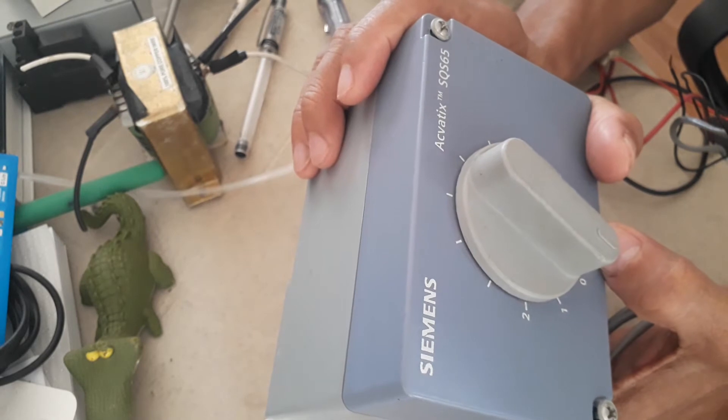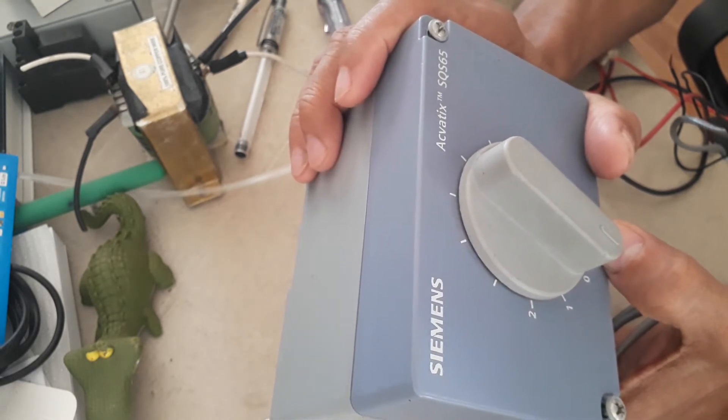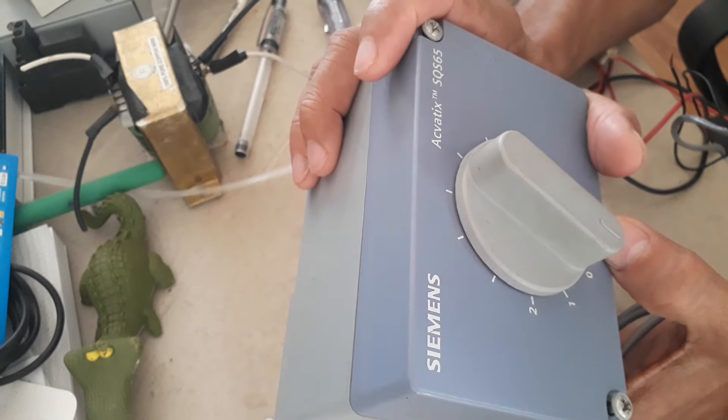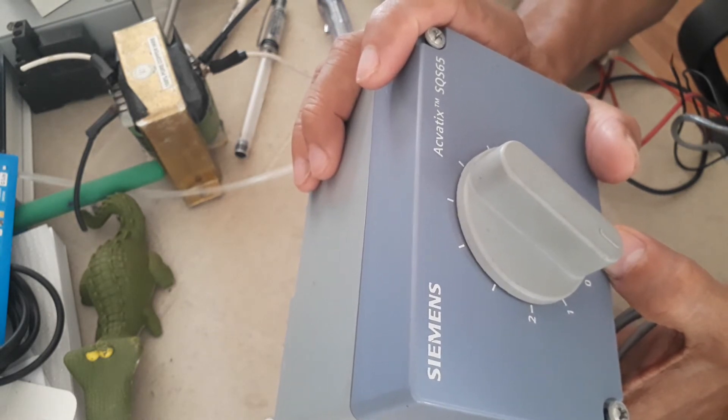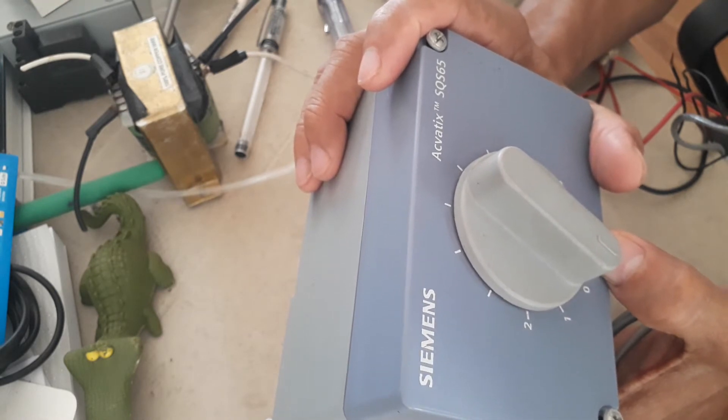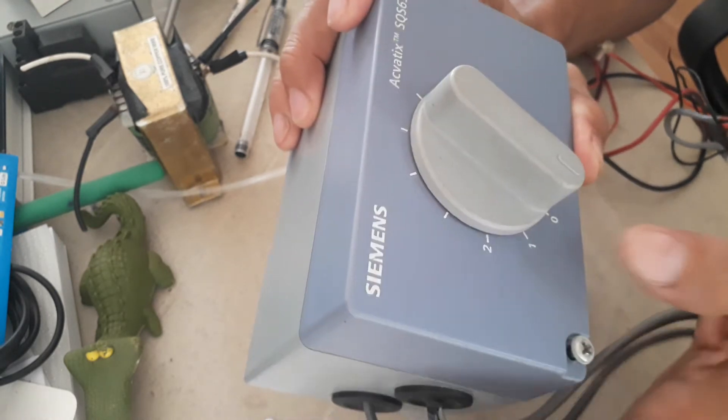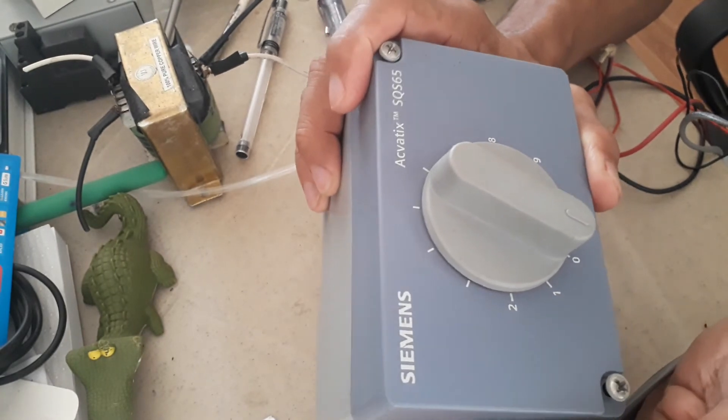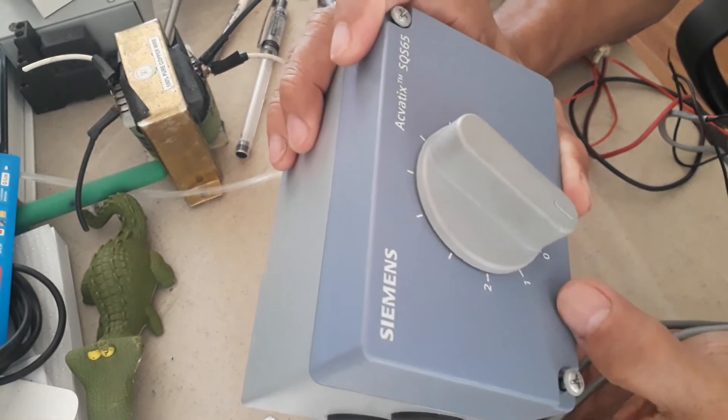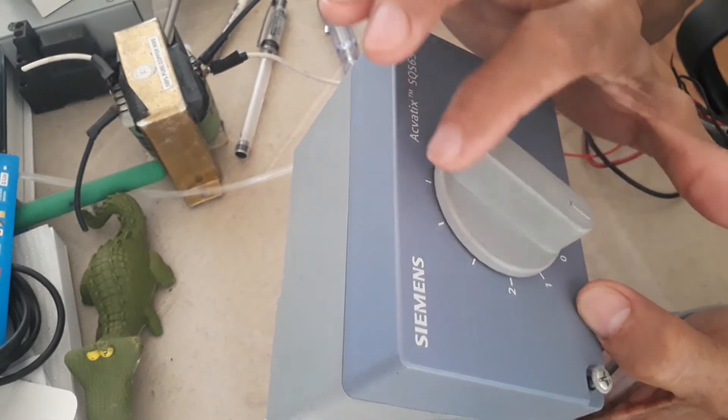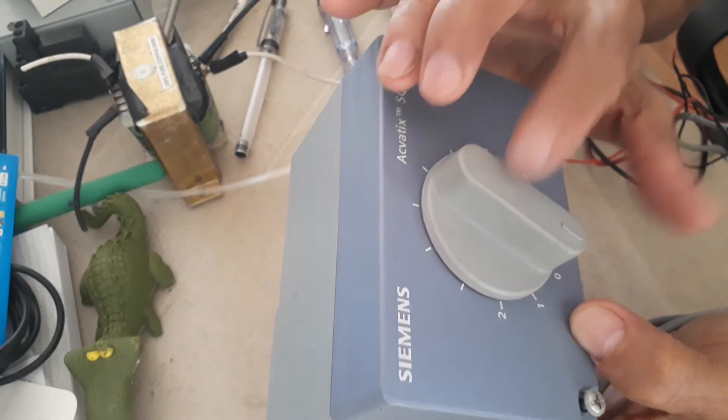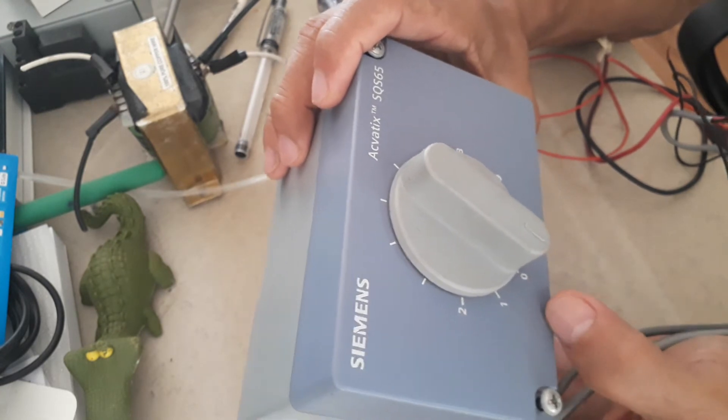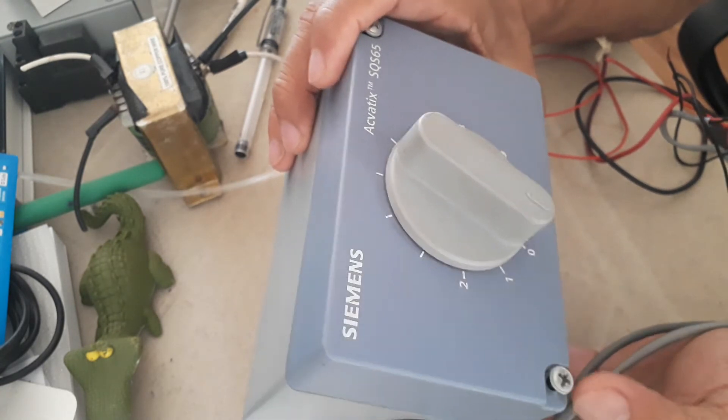When you say modulating, the control signal for this valve actuator is coming from your DDC analog output that can provide 0 to 10 volts DC that will be fed to this valve actuator. You will see if this valve actuator is working by just looking at this knob. Right now, it is in closed position.